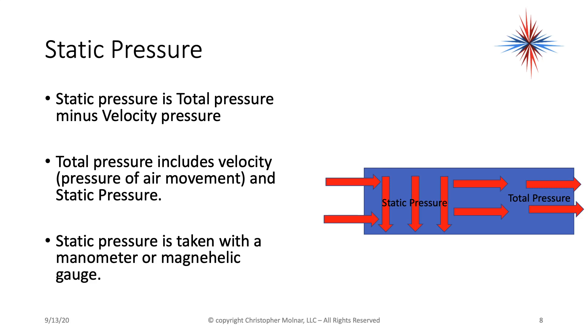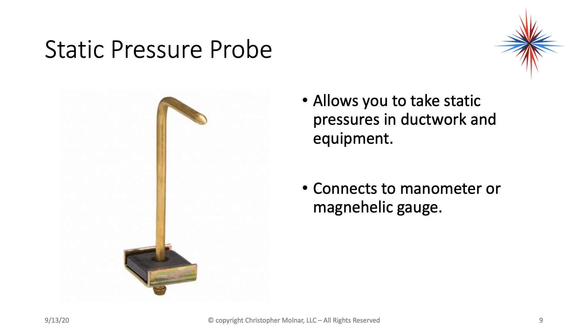Static pressure is the total pressure minus the velocity pressure. Looking at my diagram: I have air blowing through the ductwork. If I measure the pressure of the air in this airstream, I'm getting total pressure. So I have to remove the pressure of the air moving to find the static pressure, which is the outward pressure against the sides of the ductwork or equipment. Static pressure is taken with a manometer or magnehelic gauge using a static pressure probe, which connects to the gauge and removes the velocity pressure from the measurement.